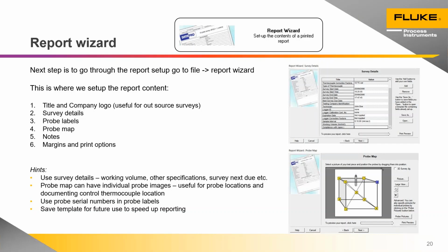Something to note here is that in addition to the wireframe or the photograph showing exactly where the thermocouples were placed, you can take pictures of the individual thermocouples very close up and store those and link them to the thermocouple. They will be printed on the report, and that's another really useful thing to realize, is that if you get a question when you're presenting the report in the future and there seems to be an anomaly in the data, you can look back at exactly where the thermocouples were placed, how they were tied in place for each of them individually, simply by clicking on them.